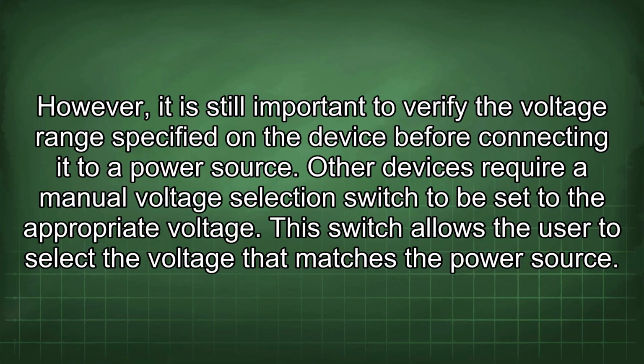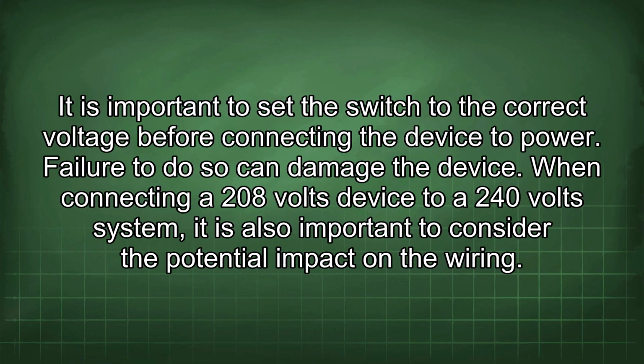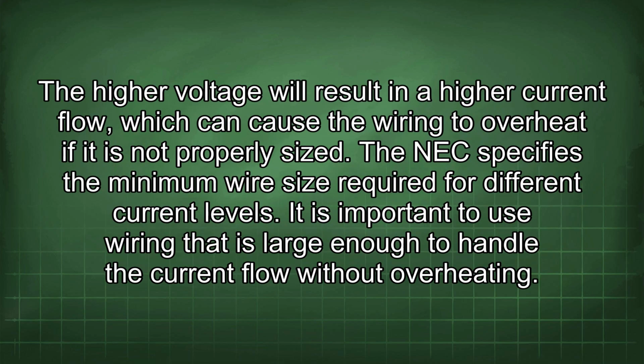source. Other devices require a manual voltage selection switch to be set to the appropriate voltage. This switch allows the user to select the voltage that matches the power source. It is important to set the switch to the correct voltage before connecting the device to power. Failure to do so can damage the device. When connecting a 208 volts device to a 240 volts system, it is also important to consider the potential impact on the wiring. The higher voltage will result in a higher current flow, which can cause the wiring to overheat if it is not properly sized.